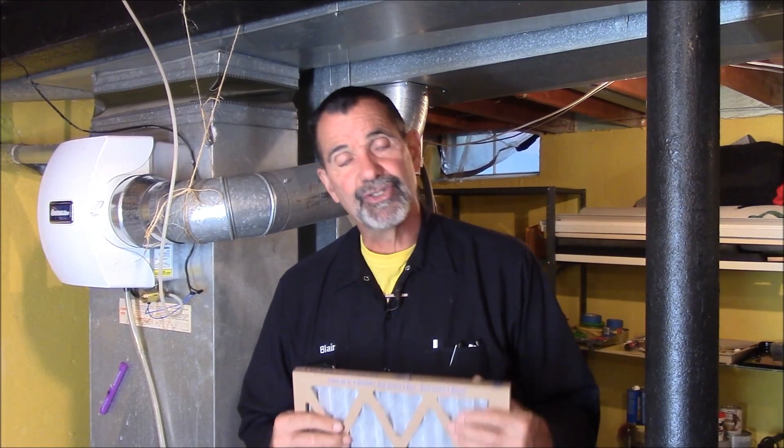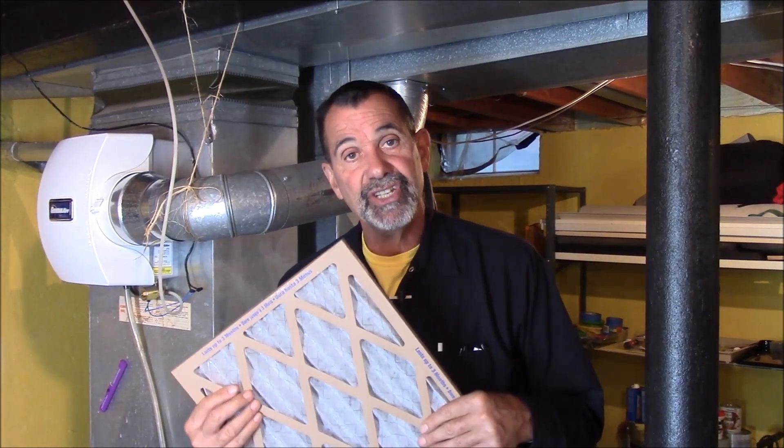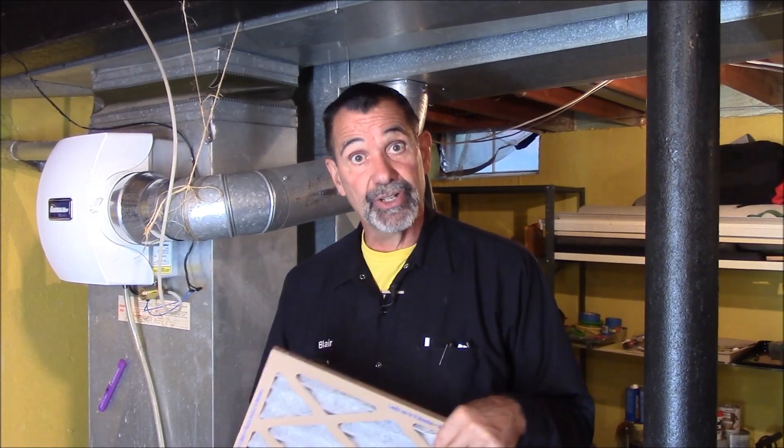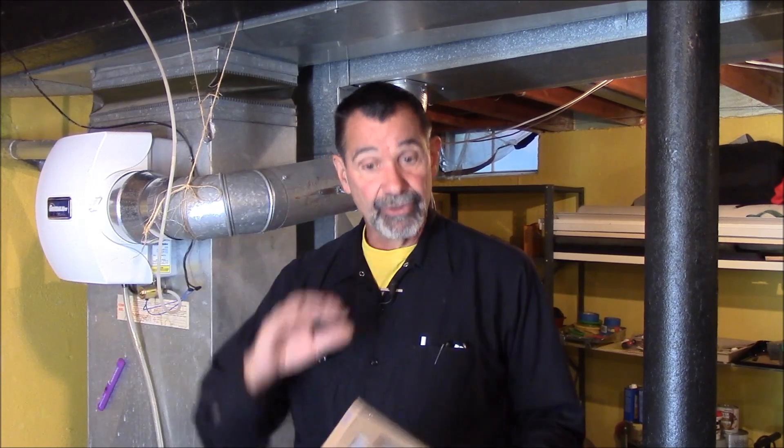What's happening is we were putting in fancy air filters into this furnace — high MERVs, a MERV 11 to a MERV 13. Good if you're asthmatic, but bad for the furnace because the furnace didn't know that this fancy air filter was coming. It was built to handle a standard fiberglass or a MERV 8 filter.